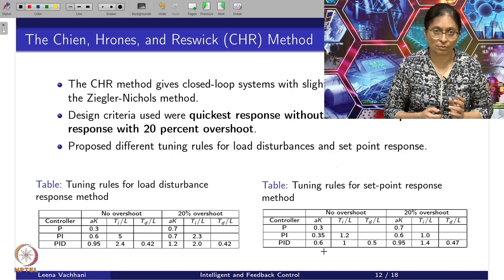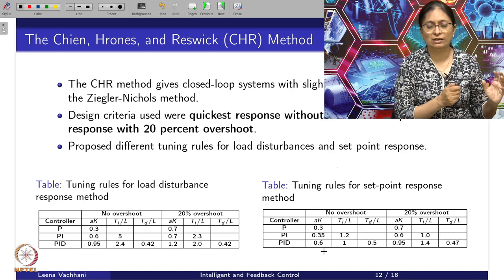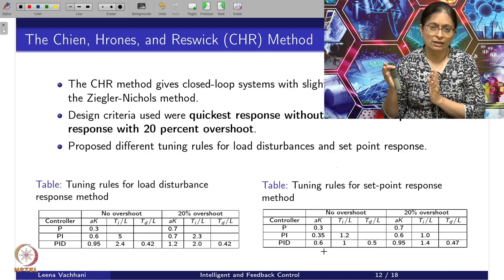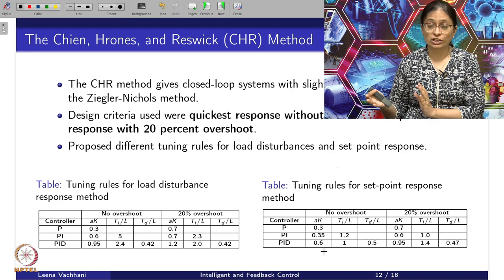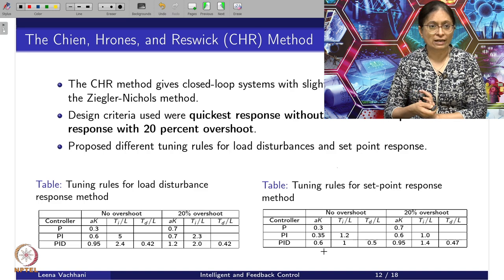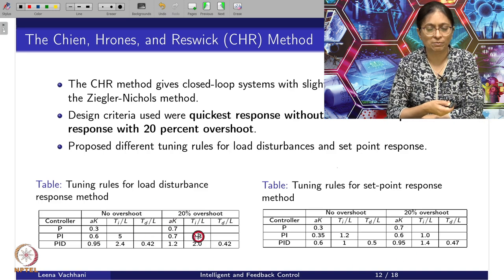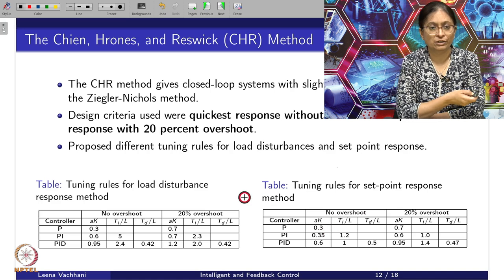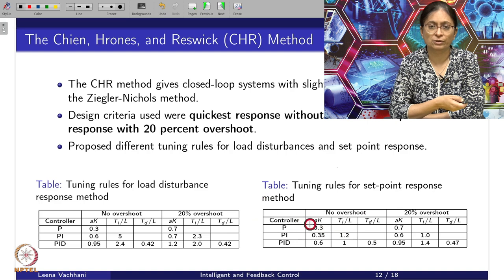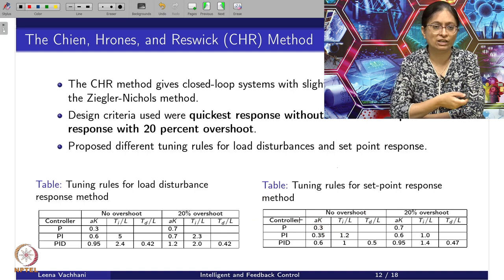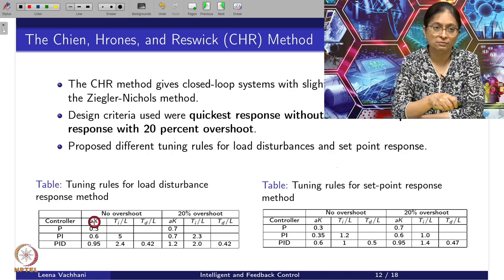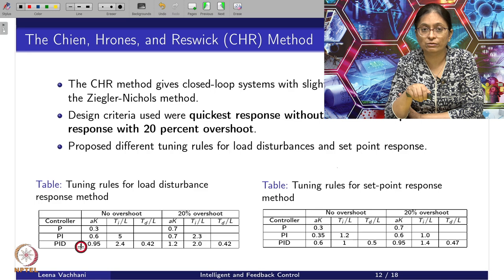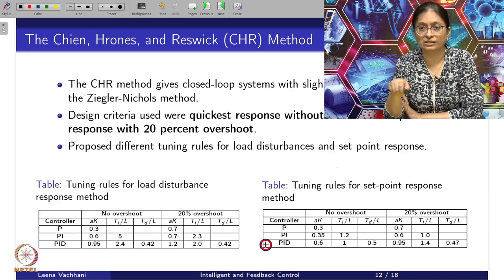At the same time, there are two different control objectives considered. One is the tuning rule if you are considering load disturbance rejection as the criteria, and there is another set of tuning rules if you are considering set point response as the control criteria. Looking at the comparison between no overshoot and 20 percent overshoot with respect to tuning rules for the set point response method, we see that the proportional control tuning rule is the same — for example, for no overshoot the proportional gain is 0.3, and similarly for load disturbance the proportional gain is also 0.3.